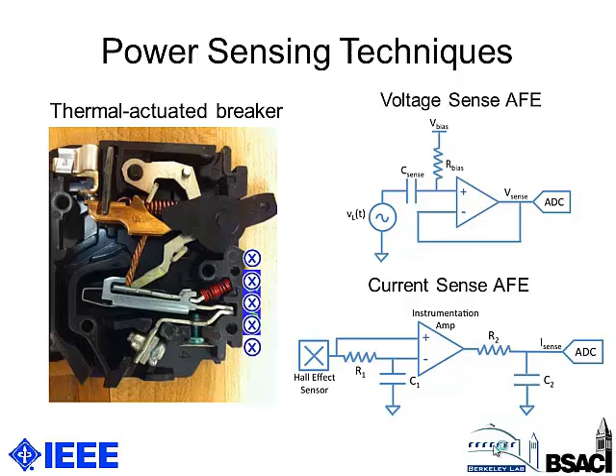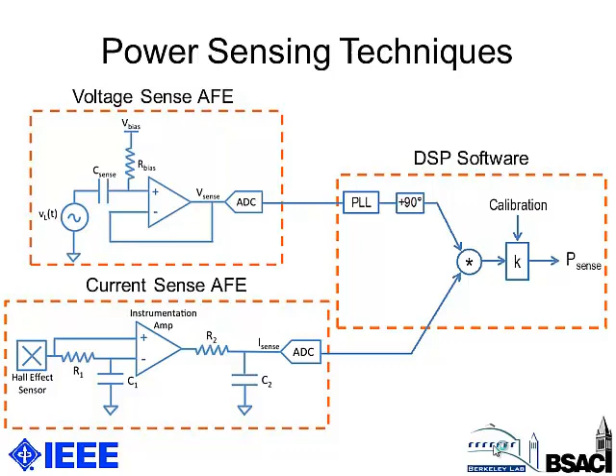The sensed voltage signal is proportional to the derivative of the actual line voltage, resulting in a minus 90 degree phase shift on the sinusoid. So we built a PLL in software which tracks the phase of this voltage sense signal and implements a positive 90 degree phase shift to account for the derivative. The output is then multiplied by our current signal, and the result is scaled by a factor K from a calibration, which I'll discuss later. The output of that calibration block is power in watts.